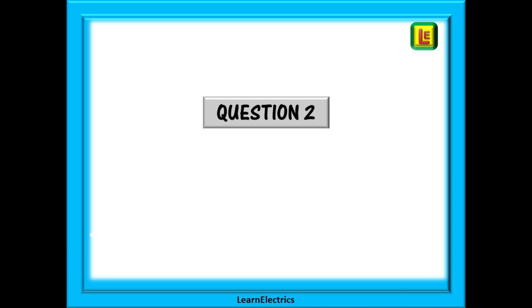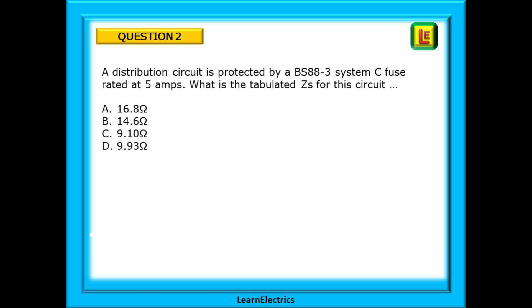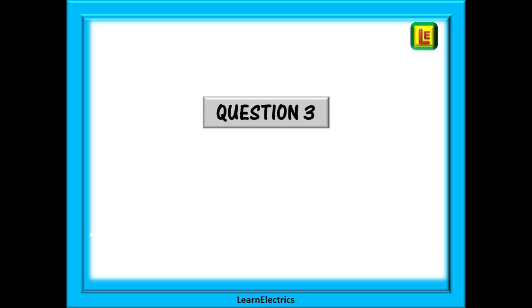On to question 2. A distribution circuit is protected by a BS88-3 system C fuse rated at 5 amps. What is the tabulated ZS for this circuit? Again, pause the video whilst you find the answer. You should have answer B, 14.6 ohms. As before, the information in the box shows you the route to the answer.